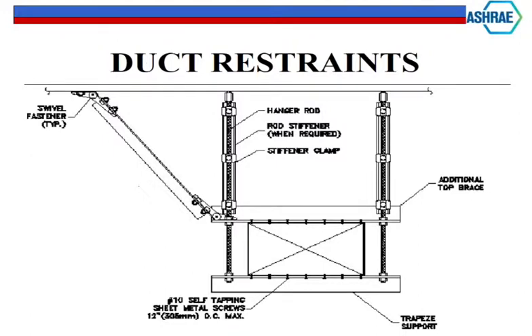So ductwork, just like piping, can be done with bracing. Here I show steel bracing this time, so that's just one-sided. Whereas with the cable, you had two cables going off the side because cables only work in tension, they don't work in compression. Steel works in both compression and tension. But one of the big problems with ductwork is such light gauge. You cannot just bolt onto a piece of ductwork. It's too light.